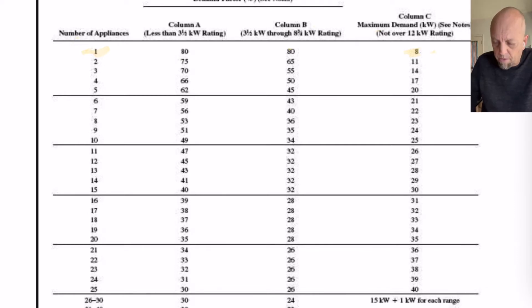So, if you have a range that goes from 9kW to 12kW, all you have to do is look in this table and they've already figured out the demand factor for you or the load. Actually, this is the load for those sizes of ranges.